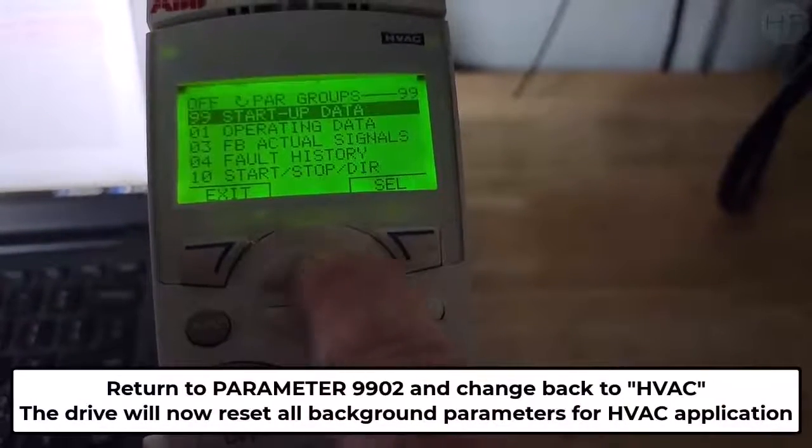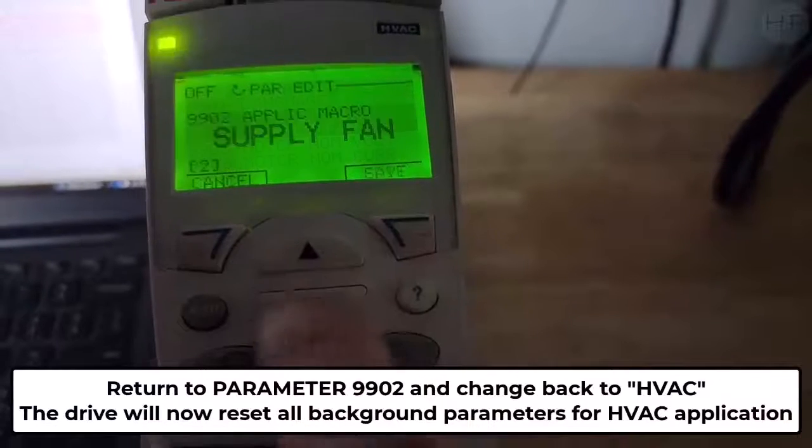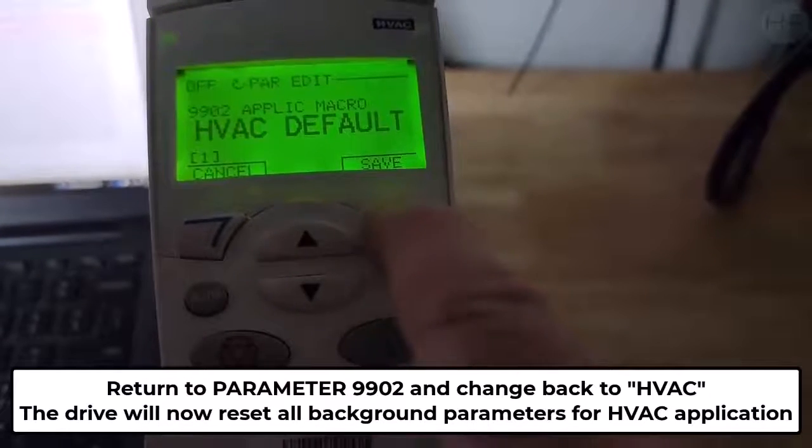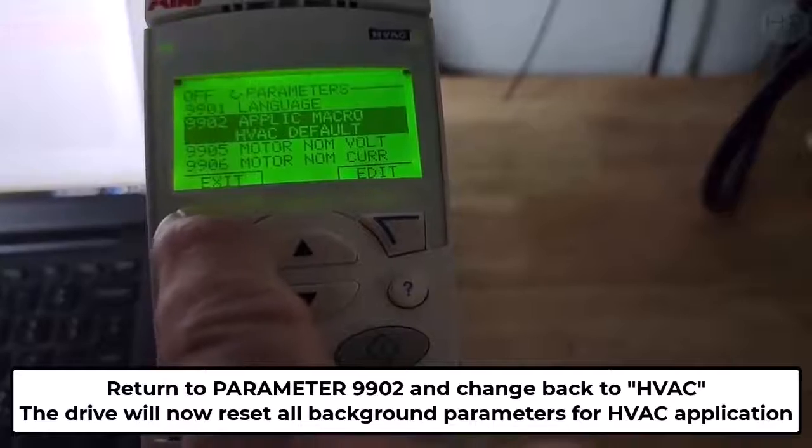Return to parameter 9902 and change it back to HVAC. The drive will now reset all background parameters for the HVAC application.